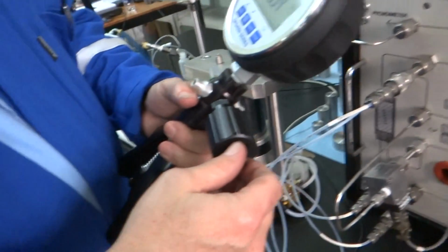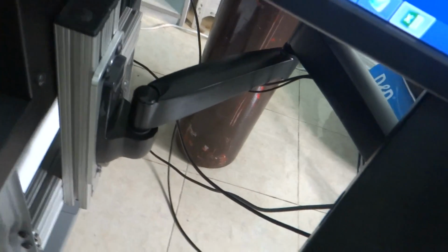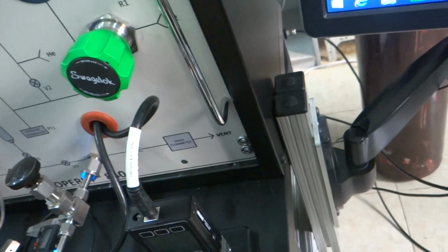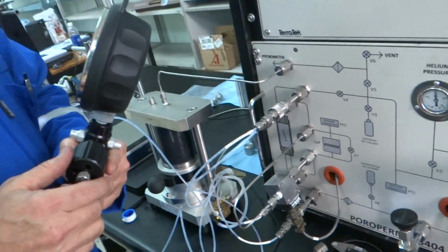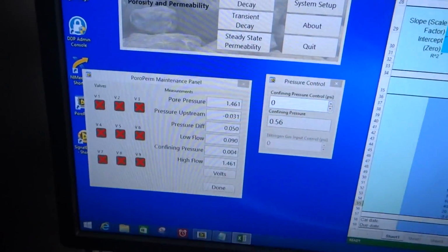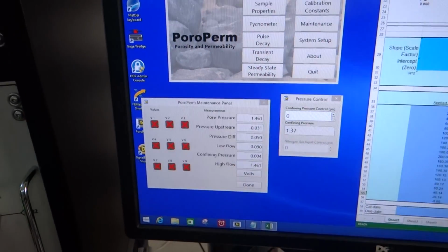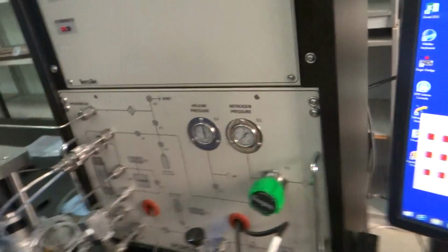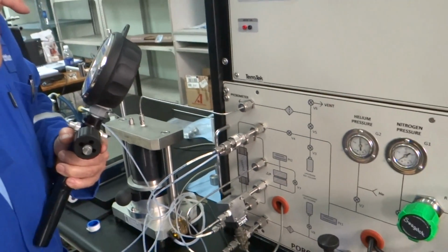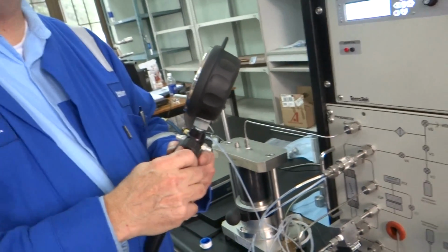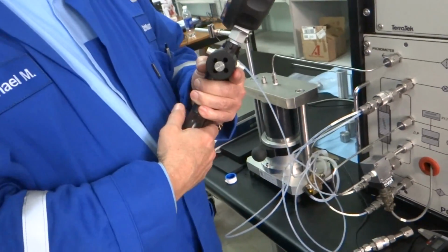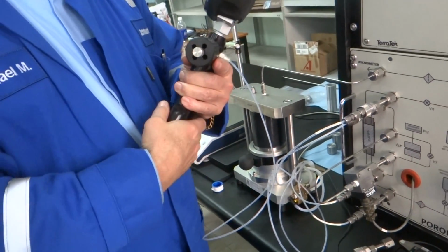But if we set 200 psi and this is more than 10 volts, then you reduce the gain. Between 9.5 and 9.8 volts. Okay. So when you go back down after you adjust the gain, the zero voltage will be wrong, and you'll have to adjust the offset to re-zero it again, and then pump it back up and check the gain again. You might have to do it 2 or 3 times to get it in.